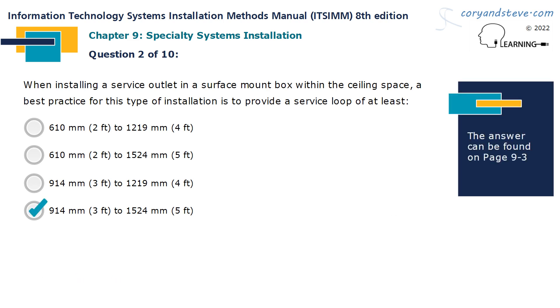When installing a service outlet in a surface mount box within the ceiling space, a best practice for this type of installation is to provide a service loop of at least 914 millimeters (3 feet) to 1524 millimeters (5 feet).